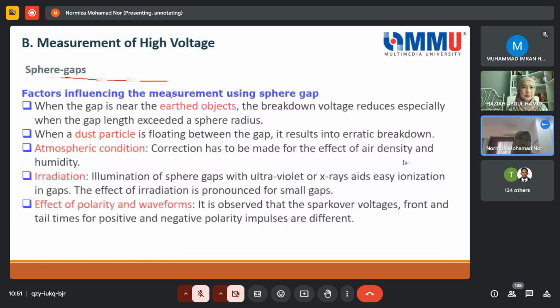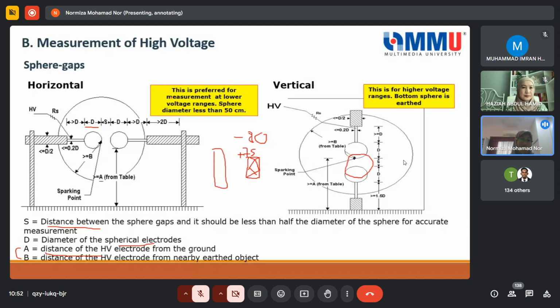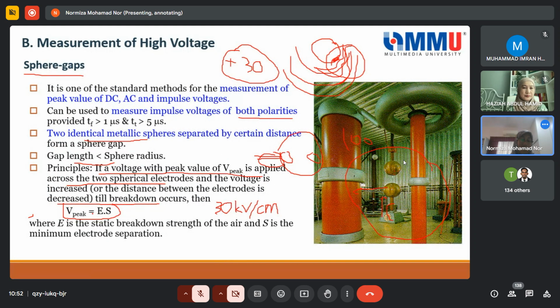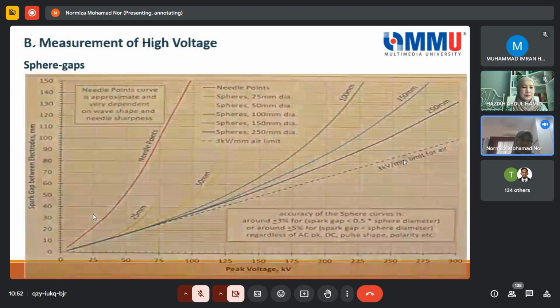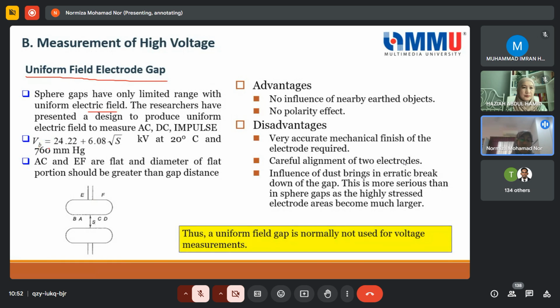Whereas just now for the sphere gap it is straightforward, where V equals E multiplied by S. But for the uniform field gap, V is 24.22 times the gap distance plus 6.08 times the square root of the gap distance, in kV, for the atmospheric condition. So you can see here there's a flat surface, compared to the sphere gap, which is very much round. The advantages you can consider as the disadvantages of the sphere gap. The sphere gap is influenced by nearby earthed objects, but the uniform field gap has no influence of nearby earthed objects.